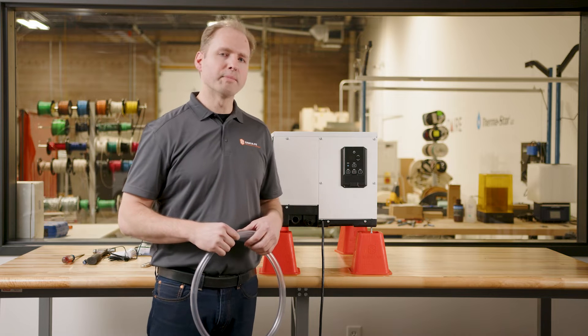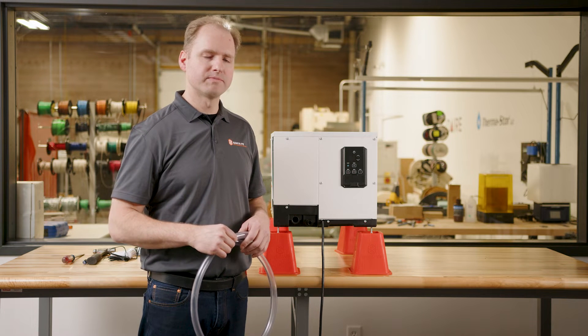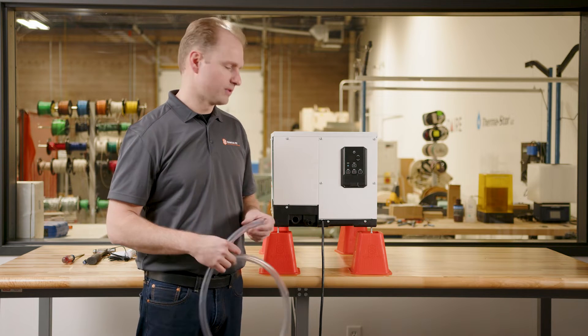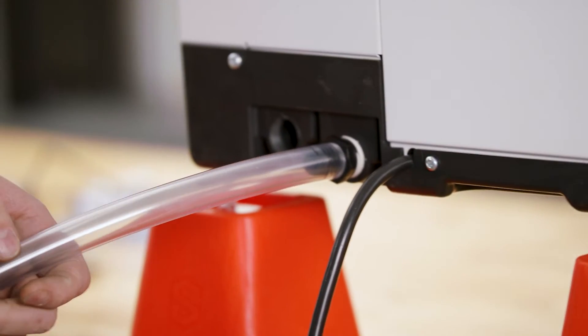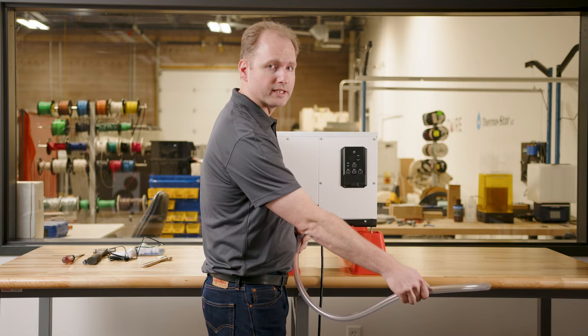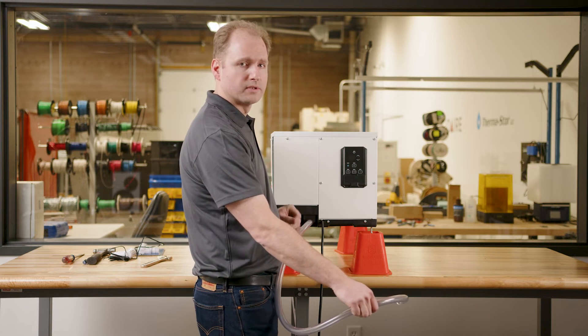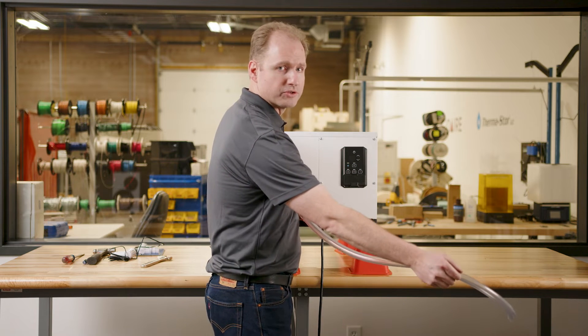This unit also uses a positive pressure drain pan, so a drain trap is not required. Simply install the hose and run the drain line to your drain. Make sure the end of the drain line is not below water and there is a pitch down to the drain.